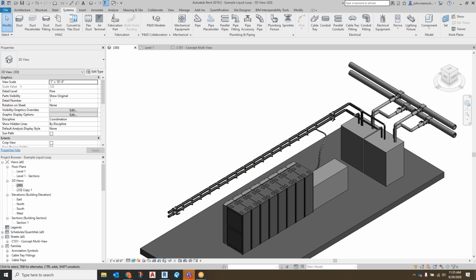Likewise, if you've got a 6-inch connection and a 9C delta T, maybe you can support X number of kW. So it wasn't so much to drive the engineering people as it was to help the IT planners figure out what's feasible from a cooling perspective.